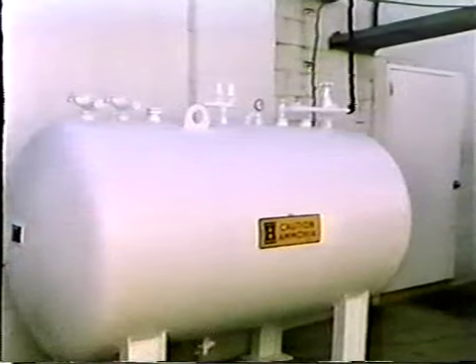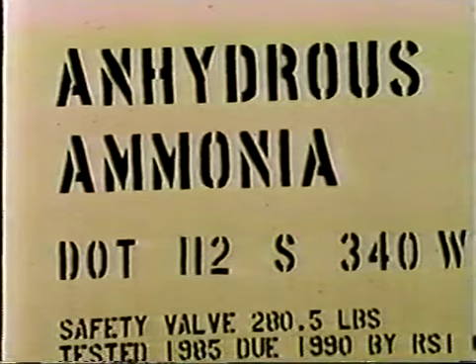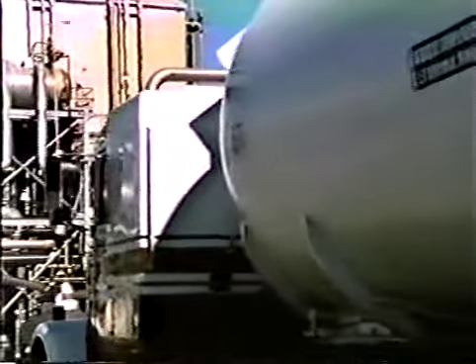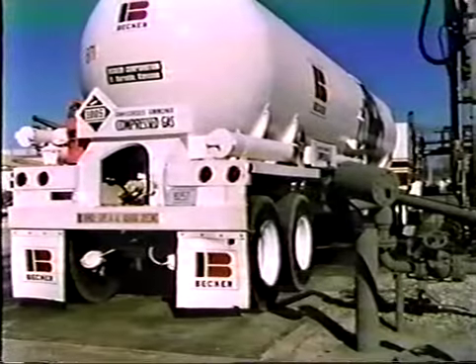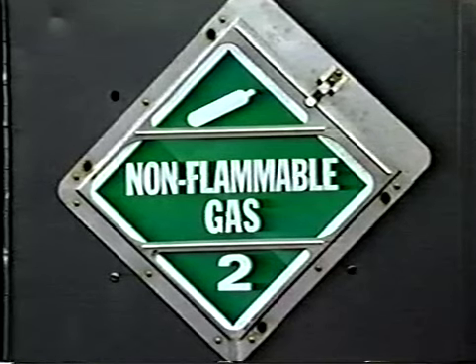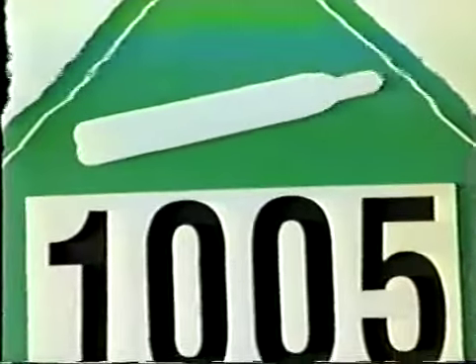All tanks must be specially manufactured for anhydrous ammonia service. Most containers are required to have pressure relief devices, but they are not required in cylinders of less than 165 pounds capacity. Certain ammonia tanks may be used interchangeably to ship LPG, so emergency responders must beware and verify tank contents. Shipments must be appropriately placarded and carry the inhalation hazard label. Response personnel must look for the United Nations number 1005, which more specifically identifies the product.